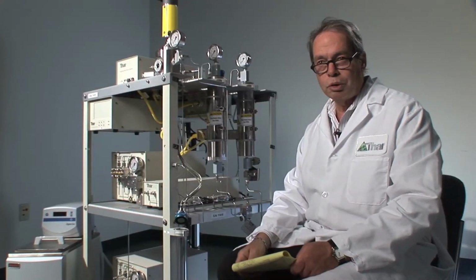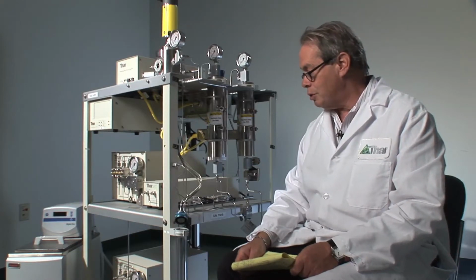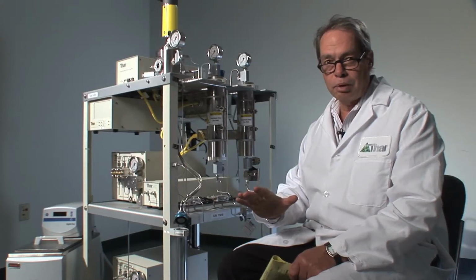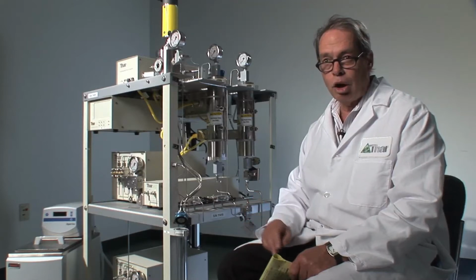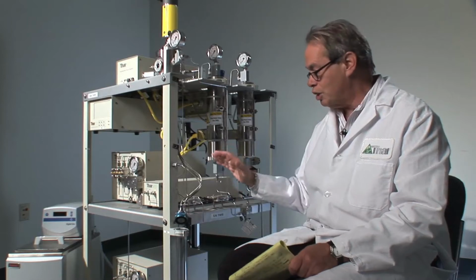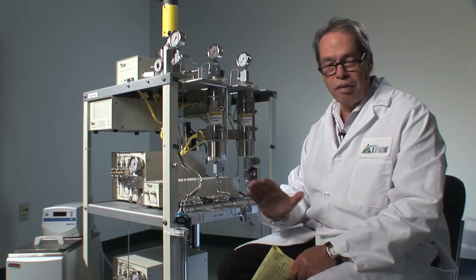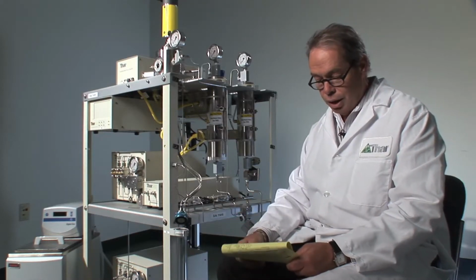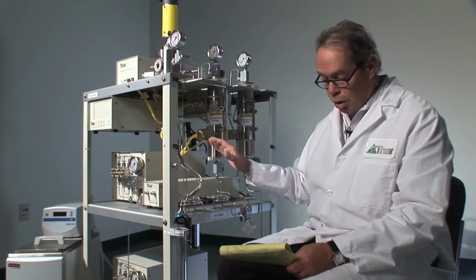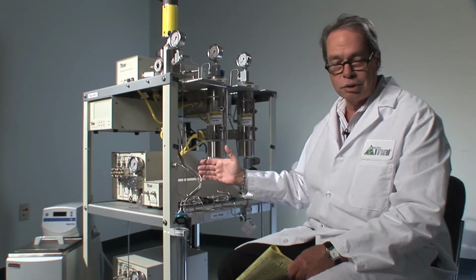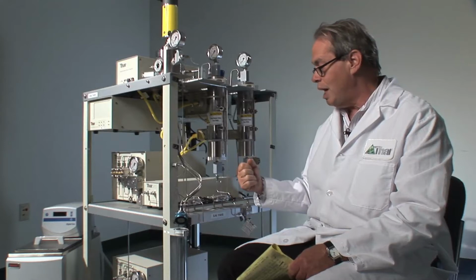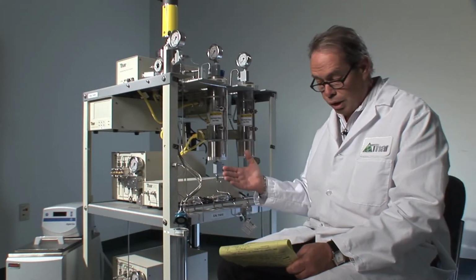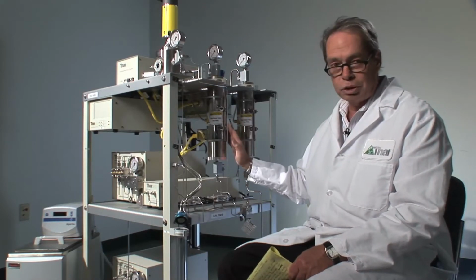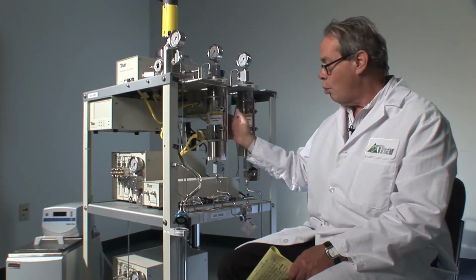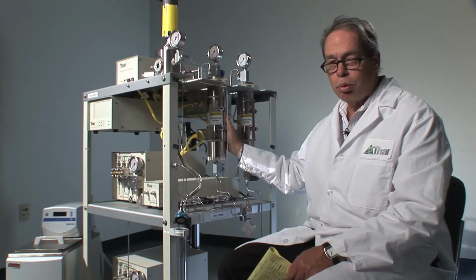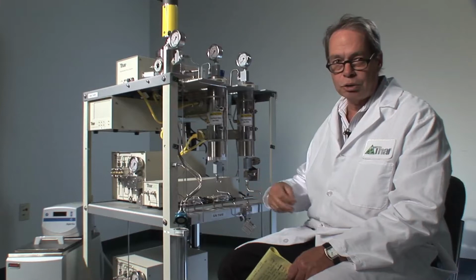Compared to other commercially available supercritical fluid extraction systems, this one has some unique features. First, it is completely automated in its operation. The competing SFE equipment is operated in a manual mode. Compared to traditional Soxhlet extraction, SFE offers the use of environmentally friendly CO2, so it's a green technology compared to solvent extraction with a Soxhlet. Much lower operating costs because you're using much smaller amounts of solvent and thus lower solvent costs as well as lower solvent disposal costs. Much lower extraction temperatures are also used in this system. The critical temperature for carbon dioxide is 31 degrees centigrade, and so one can perform extractions at very low temperatures. This is important when you're extracting thermally labile compounds from natural products.